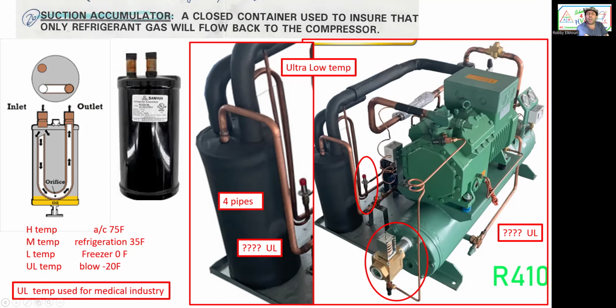A student graduated and now he's working on ultra cold, the machine that keeps embryos frozen. That's something above my scale. I never worked in ultra cold. This suction accumulator has 4 pipes in it. I'm trying to figure out why 4 pipes, and some kind of pressure regulator or oil regulator. I'm not going to say it's oil because it's above the oil level, oil is at the bottom, but some kind of valve between the high side and the low side.